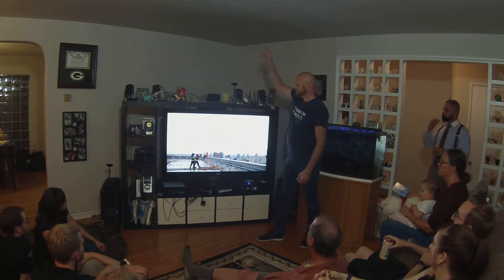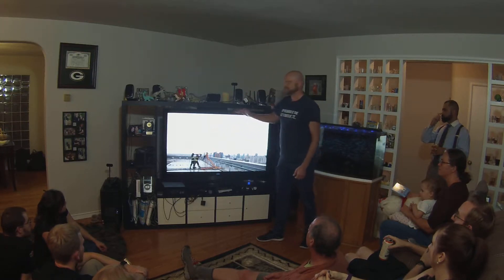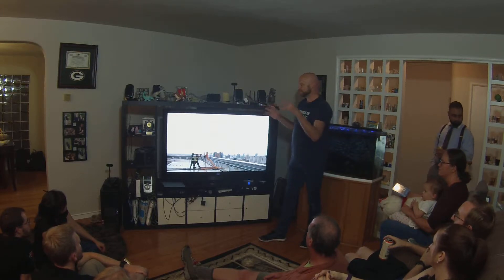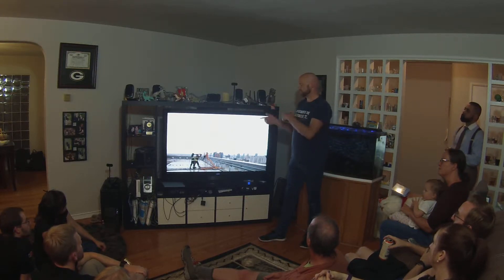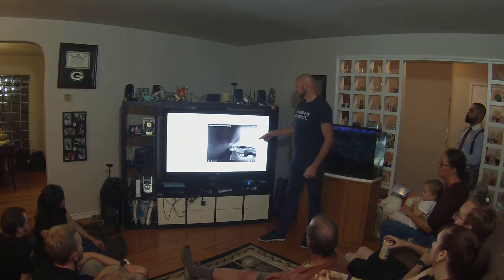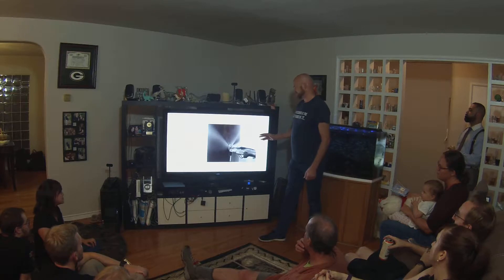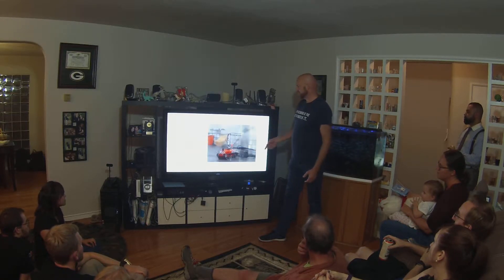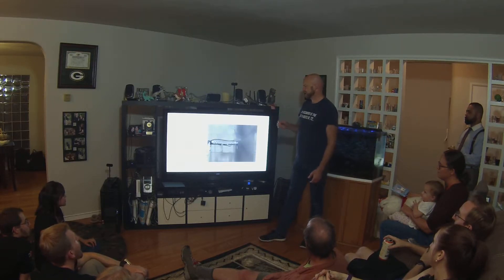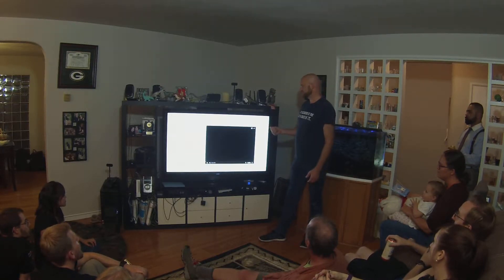This thing is useful in high-rises — at 3,000 PSI it loses less than 10% pressure on a 50-story building. If you have a small closed-up apartment, this can put the fire out by itself. There's a robot carrying one of these because it's so lightweight. It can put out flame in thatched roofs, underground, railroad cars, and shipping containers. Very useful in limited-water situations.